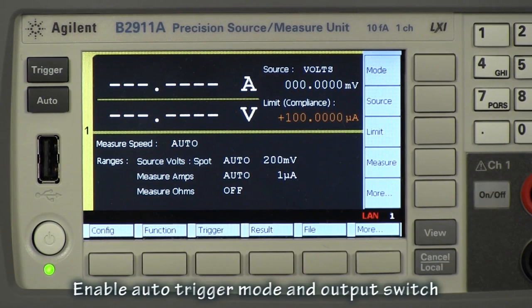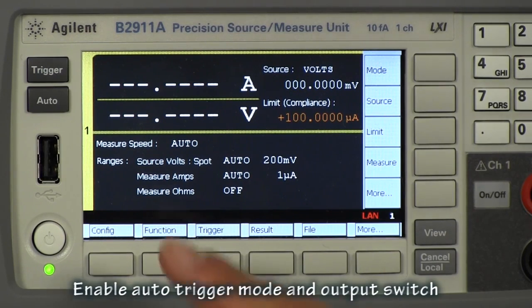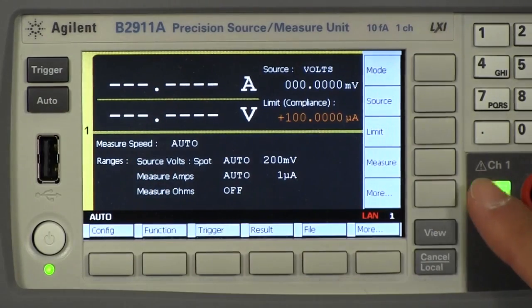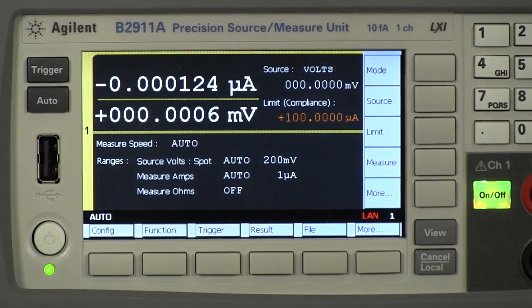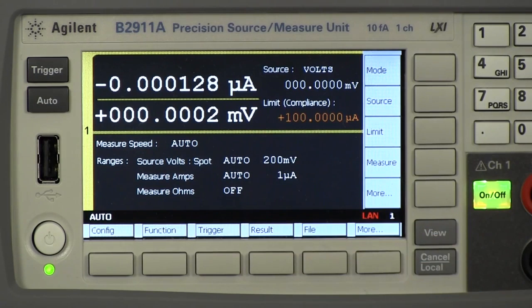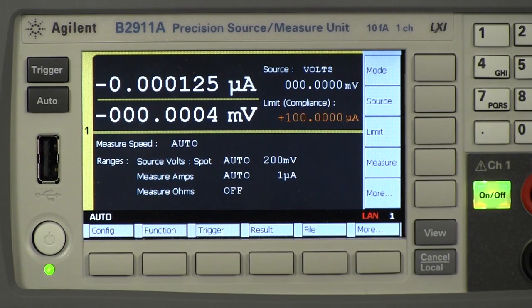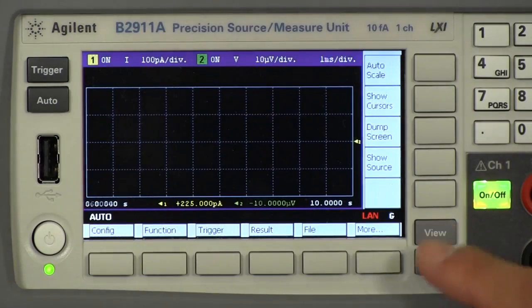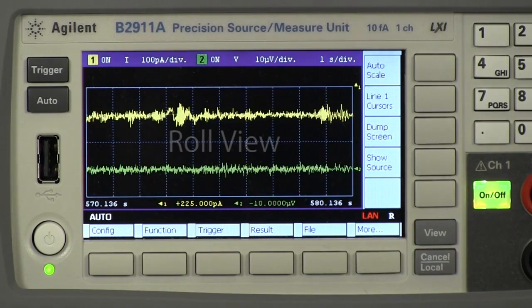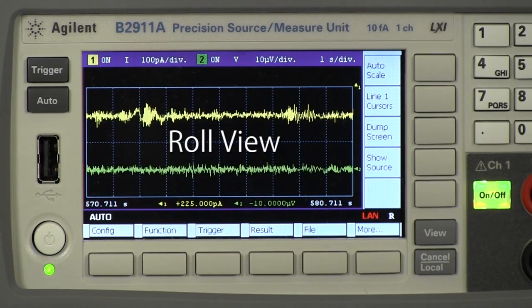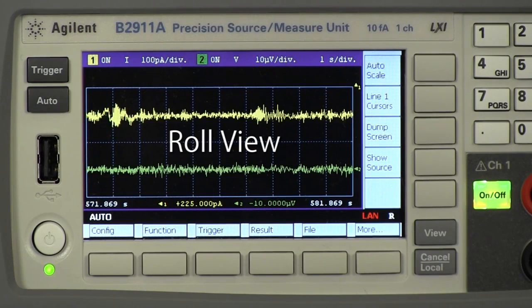All we need to do is enable auto-trigger mode and the output switch. You can see the measured current like this. You can also see the current waveform with roll view. The current waveform is updated continuously.